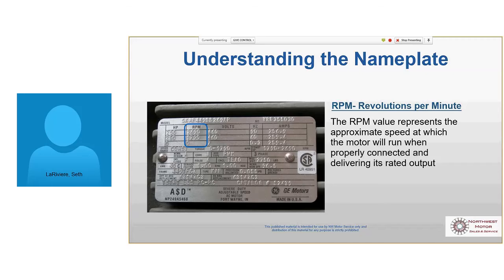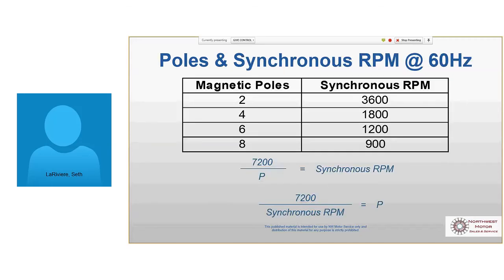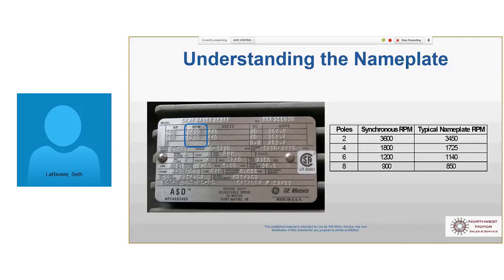RPM, of course, is going to be on there. That's on everybody's nameplate. This is that formula we showed you earlier, for 2, 4, 6, 8 poles, and then the actual speed. So this is a synchronous speed. This is the nominal speed here, actual speed, 3450. The difference is slip, and we're going to get into that in a second.